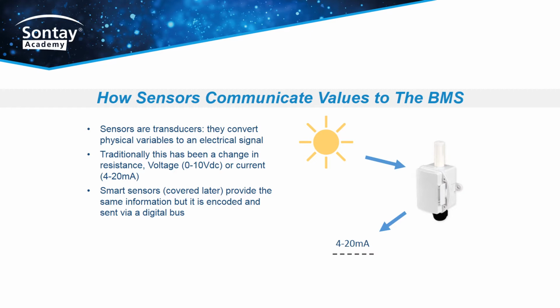The BMS industry uses 3 common signal types for sensors. Active sensors have onboard electronics which provide a linear output voltage or current signal. Although other scales exist, the most common active signals are 0 to 10 volts DC or 4 to 20 milliamp.